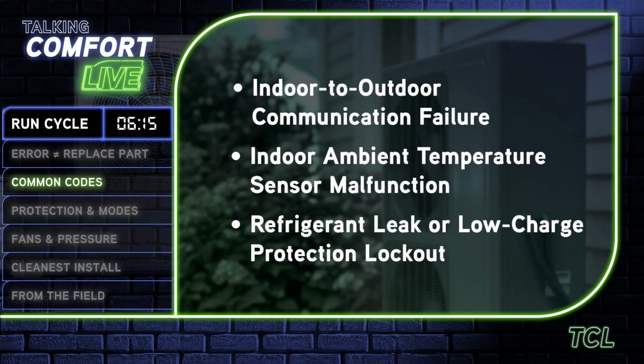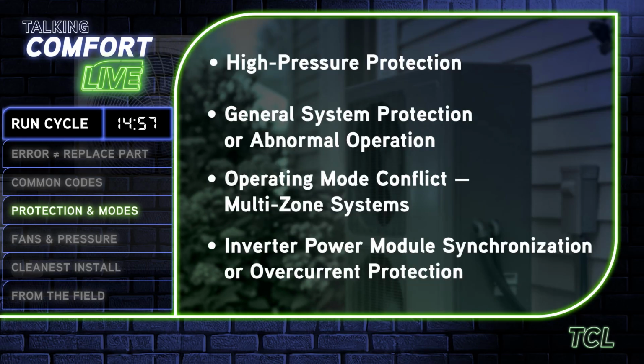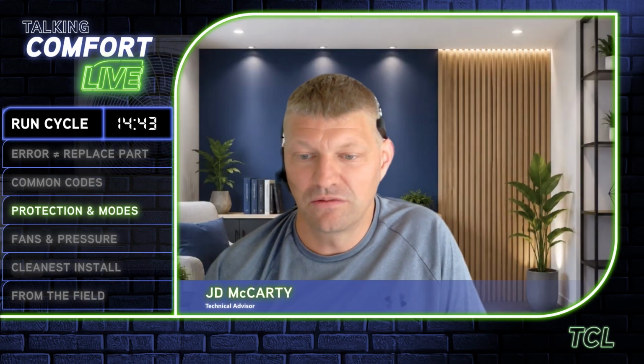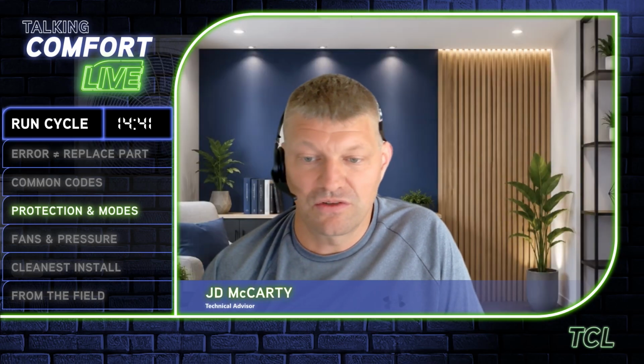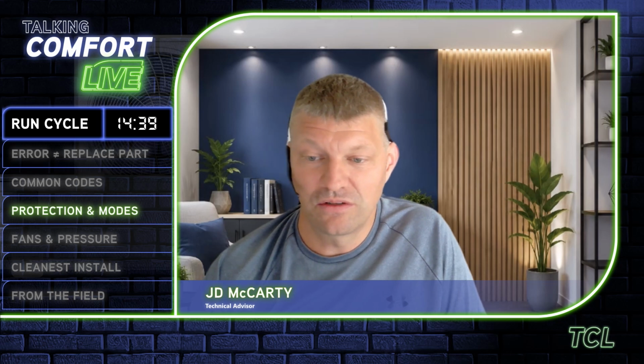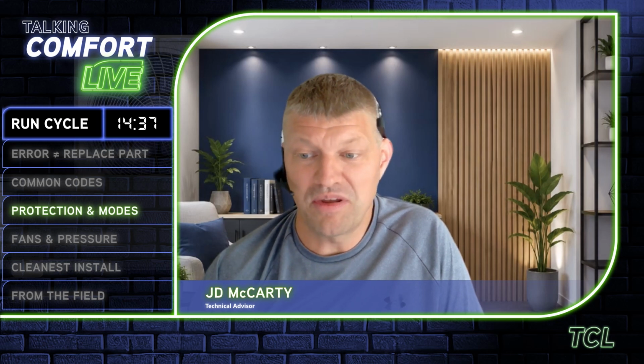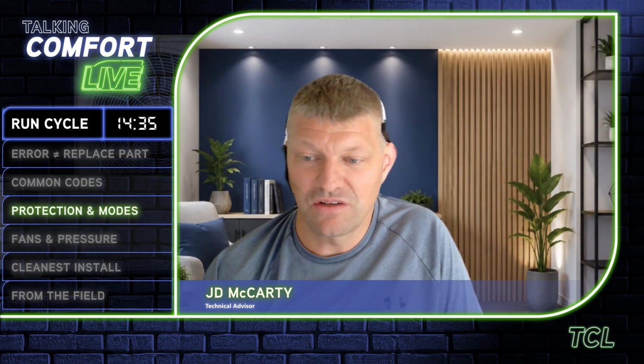Protection and modes. So let's continue with fault, pressure, system, mode, and inverter protection faults. What's that first one there, JD? All right, so the first one is high pressure protection. A couple different codes here. On Gree, it's going to be an E1 code. On Aux and Midea, a P1, and on Daikin, it's going to be an E3 code.